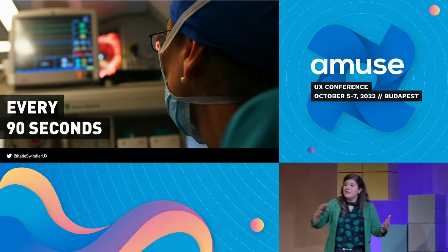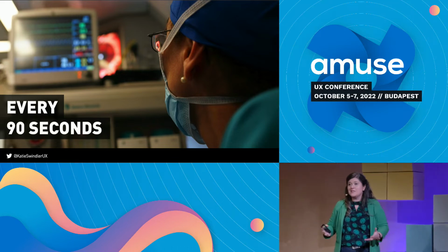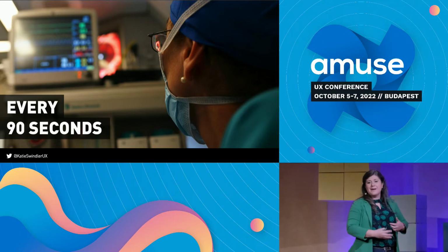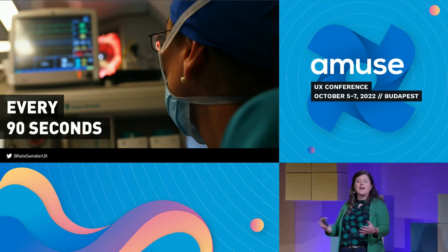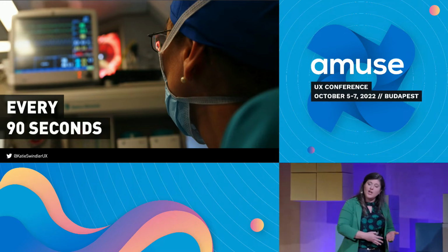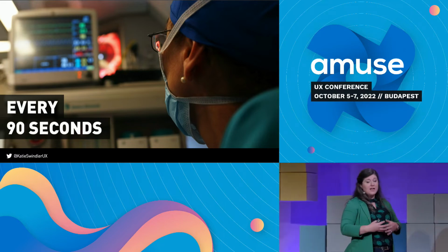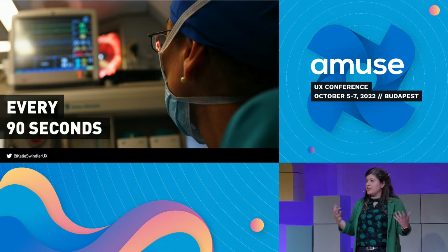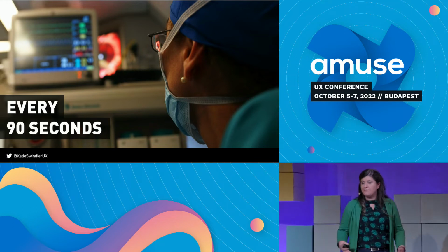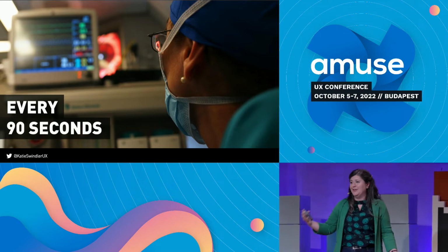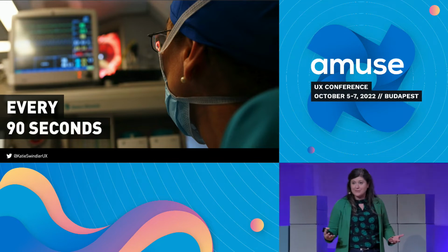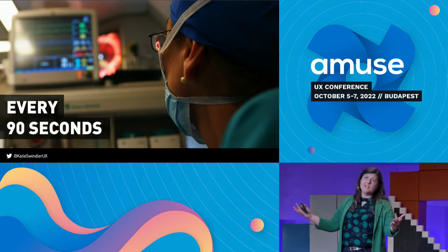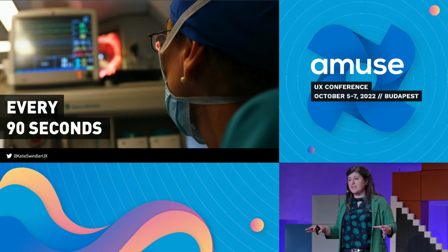And again, all of these alarms typically are just some form of that beeping sound, sometimes with different tones, sometimes with different rhythms, but studies have shown they are not at all intuitively understood. So the low quality and high quantity of these alarms have created a real problem in the medical field. They call it alarm fatigue. Essentially, medical professionals just stop responding to them. They'll turn off critical alarm systems and then not be able to respond when something actually goes wrong. A study was done in 2013 that linked this to hundreds of patients' deaths.